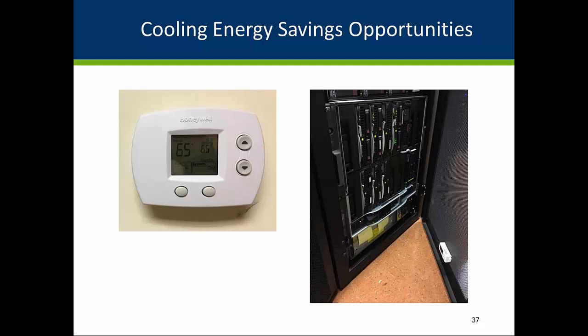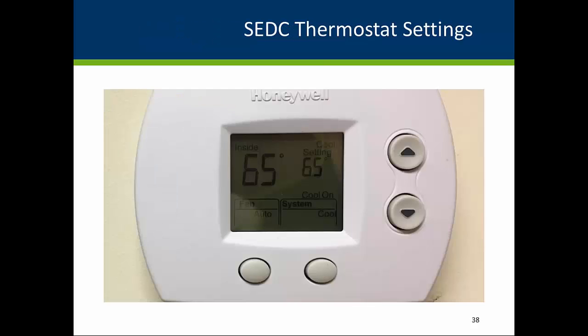Most of the SEDCs with dedicated cooling in this study have their thermostats set at temperatures in the low to mid-60s. With knowledge of the rack inlet temperatures, energy savings opportunities exist by reducing the cooling load of the SEDC through more efficient delivery of cool air to the server racks, and consequently by raising the thermostat set point temperature. At 3 sites, we were able to increase the thermostat set point temperatures 3 to 4 degrees from the mid-60s to the upper 60s. This resulted in cooling load reductions ranging from 7 to 50%.